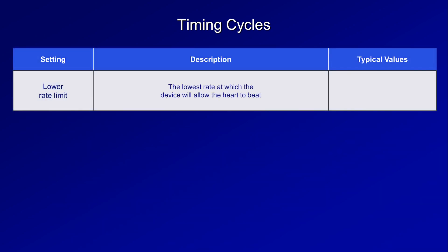The first is the lower rate limit, which is the lowest rate at which the device will allow the heart to beat. Typical values are 50 to 60 beats per minute. Although a heart rate in the 50s might intuitively feel slow since many consider this bradycardic, there's generally no harm from rates this slow, at least while at rest.